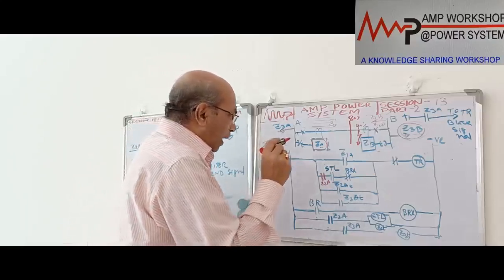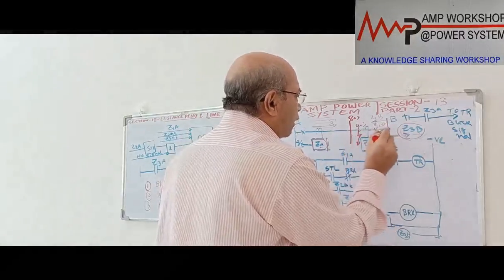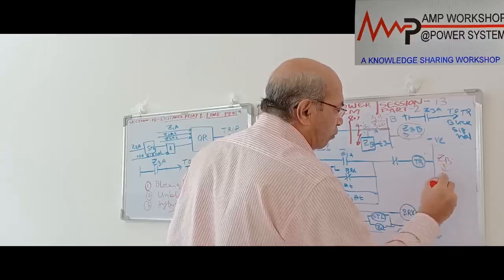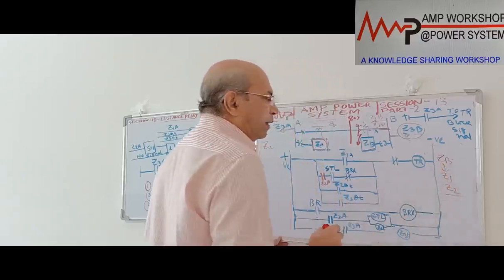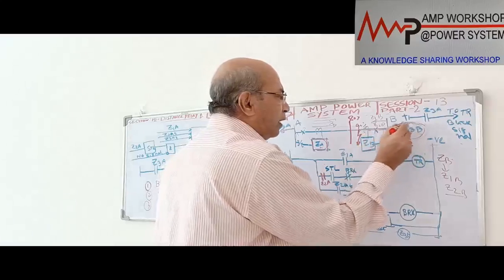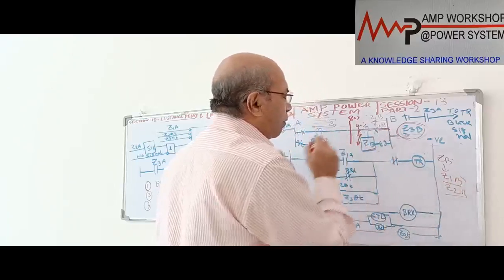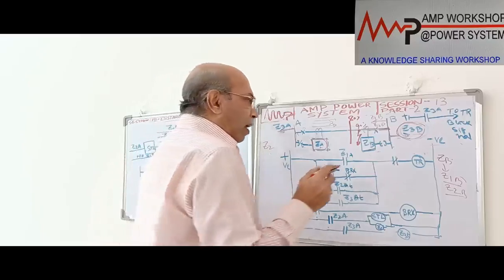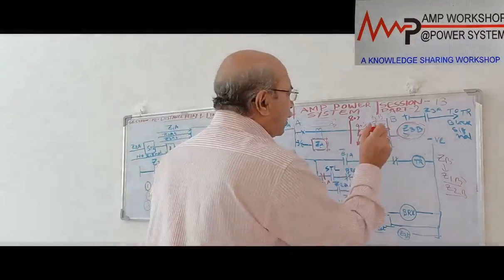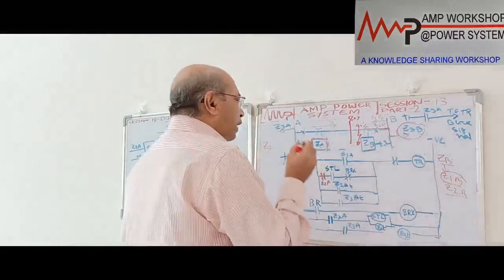Now, at the same time, what is happening over here? If there is a feed over here, when the fault is within 10% of this end, for this ZB relay, Z1 will be looking at the fault, Z2 will be looking at the fault, right? But Z3B is looking in this direction, so Z3B will not see this fault. The moment Z1B sees the fault, Z1 will operate immediately.